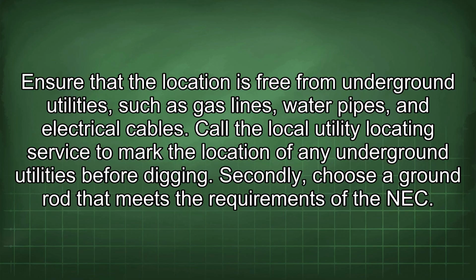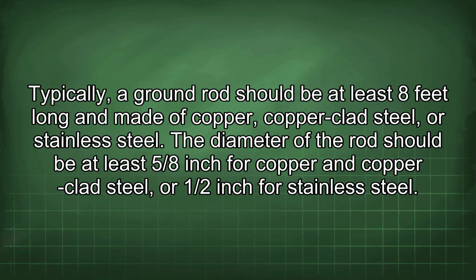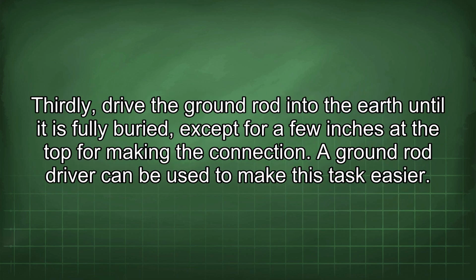Secondly, choose a ground rod that meets the requirements of the NEC. Typically, a ground rod should be at least 8 feet long and made of copper, copper-clad steel, or stainless steel. The diameter of the rod should be at least 5/8 inch for copper and copper-clad steel, or 1/2 inch for stainless steel. Thirdly, drive the ground rod into the earth until it is fully buried, except for a few inches at the top for making the connection. A ground rod driver can be used to make this task easier.